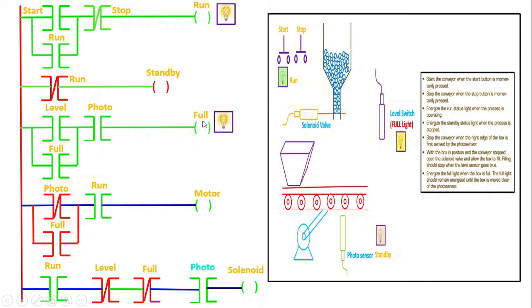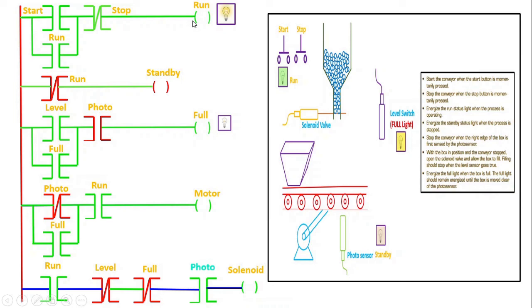There is another contact with the same address as 'full' — once full is energized here, it energizes that contact as well. Because full is energized in that rung, current flows through that path and the motor starts rotating again. The conveyor starts moving, the box moves out of the vicinity of the photosensor, and the photosensor goes back to low state — it gets de-energized. Consequently, that contact becomes open circuit and the full status light stops glowing. The process then repeats again.